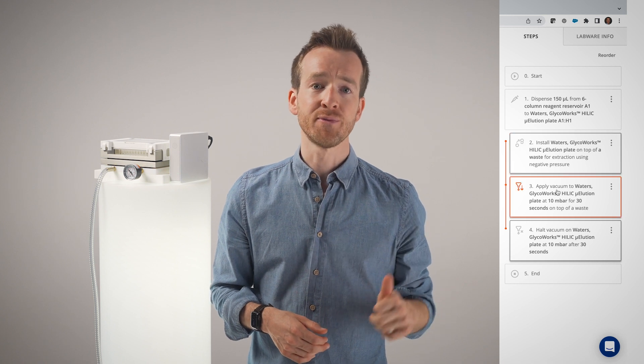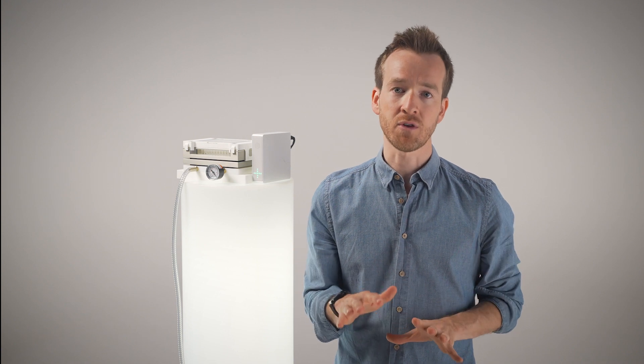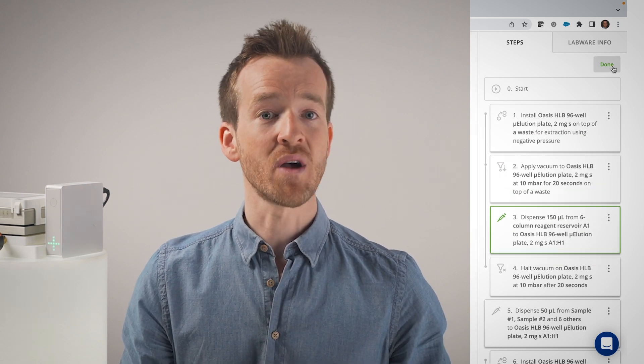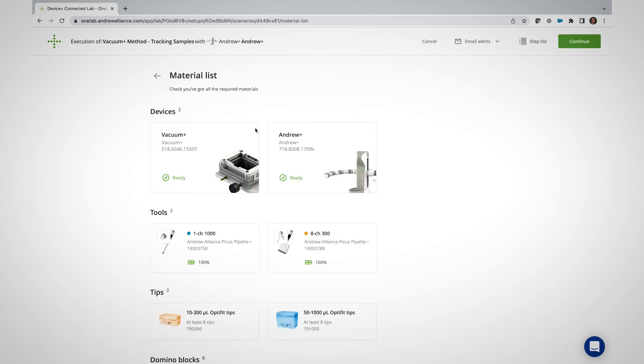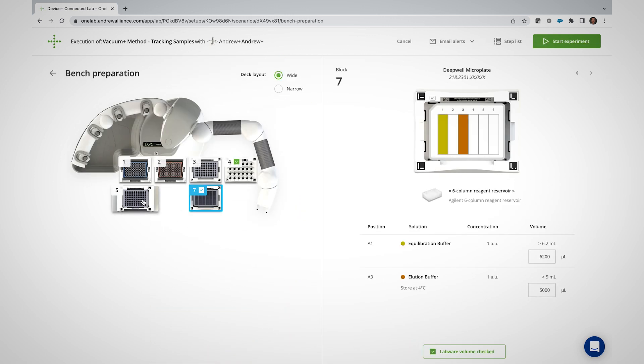Once your flow through action settings have been chosen, OneLab generates a three-part sequence with an initial labware placement step, followed by a start and a stop. Note that an extraction step like this does not require a set duration and can be event-driven. This means that the action can have embedded steps that will determine its duration, like pipetting, rather than a set timer. Once your protocol is built, click on Execute and OneLab will calculate the best configuration for your method, based on the available devices and pipettes, while suggesting different execution options. Choose the one that's most relevant to your current process, between a manual run, a guided run with the addition of connected pipettes, or an automated run, and you're good to go.